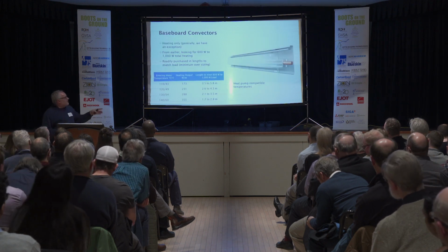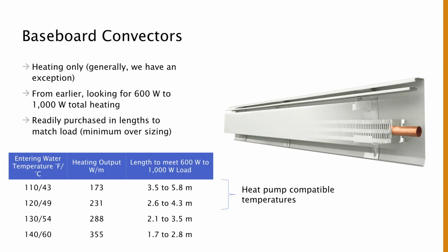We have baseboard convectors. The nice thing about baseboard convectors is they're available in any length you want. So it's pretty easy to size them for heating. There are some numbers here of what kind of load you would want to meet a 600 to 1,000 watt peak design load in a passive house suite in one of these buildings. So that's kind of nice. And at these temperatures here, they're heat pump compatible, low temperature.